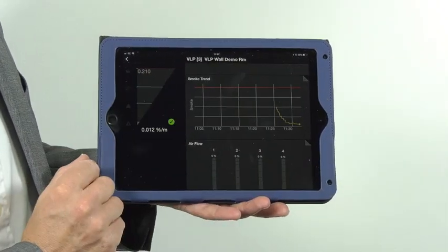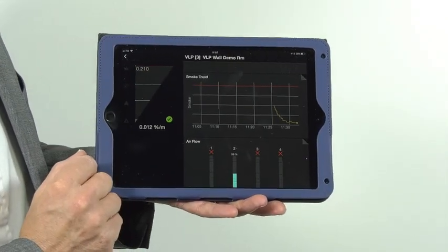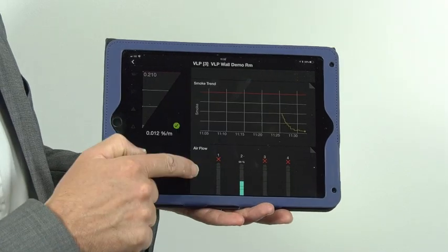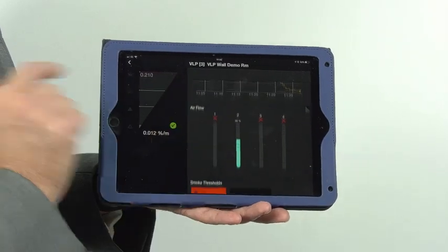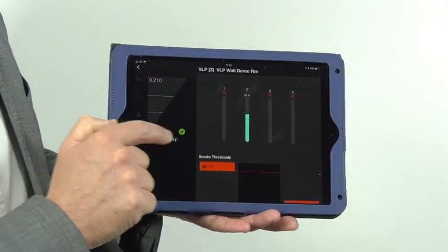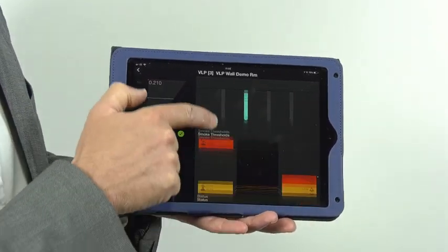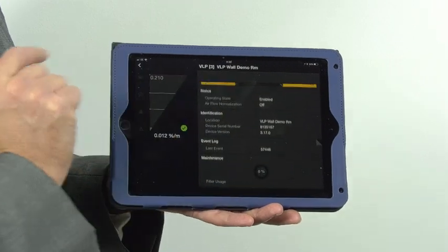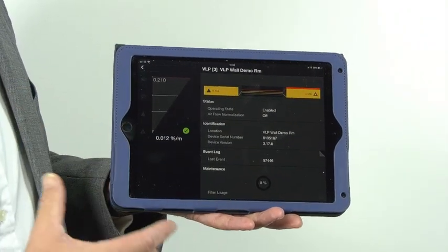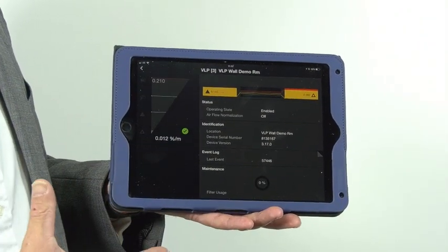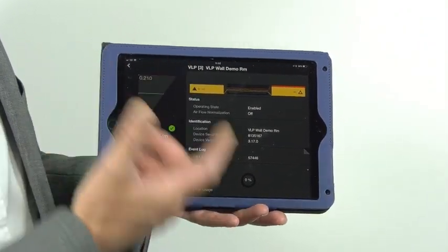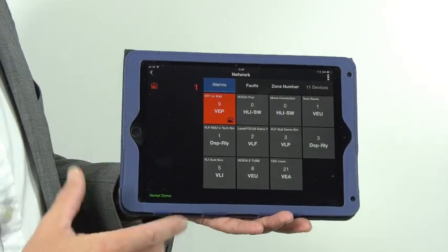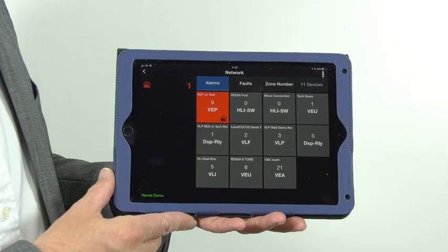We get the same level of information when we look at the laser plus. We can see the laser plus had an alarm event recently, with smoke readings, flow readings, and all the information from the VESDA-E range available on legacy products as long as there's a VESDA-E on the network.